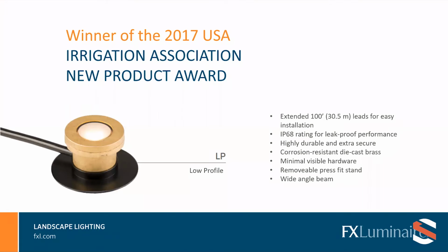And here's just one of those little lights. It's called an LP, and it's just low profile, and it literally sits in the bottom of that water feature. You can get it with up to a 100-foot cord. Remember, that fixture can be a 10-watt equivalent or a 20-watt equivalent, and it's designed for smaller water features like that fountain we saw in the last picture. We can run the wire back through a conduit and then back to the transformer, with a 25-foot cord all the way up to a 100-foot cord. But again, the nicest part is it can also be in color.